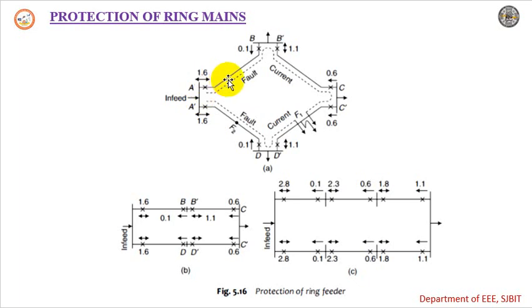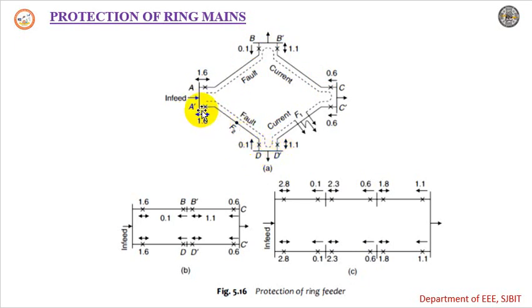For feeder AB, there is one non-directional and one directional relay. Feeder BC has one non-directional and one directional relay. Feeder CD has one directional and one non-directional relay. Similarly, feeder AD has one non-directional relay. Let us say there is a fault on the feeder between D' and C'. The fault point is indicated here, and when the fault occurs, all currents in the ring main system will try to flow towards the faulty part.